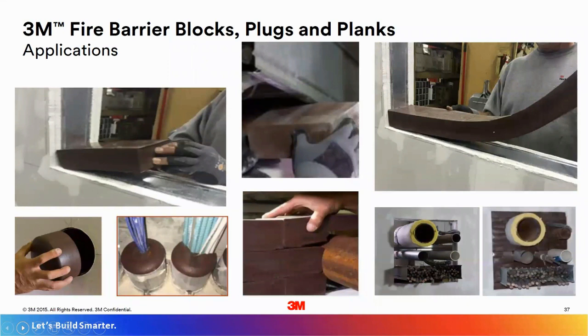And upon that urethane foam technology, we have a product called fire barrier blocks. These are available in blocks, plugs, and planks. Essentially, it's the FIP foam chemistry. These are cured material that's available in these various configurations. This is a great product to use for large openings, or if you have a situation like in the lower right-hand corner picture there, where you have a fire-rated wall assembly, for example, with multiple penetrating items. This is a great material, can quickly close down those large openings, and you would compress the material around any of the penetrating items. Any gaps, cracks, or small voids you had, you could fill with the FIP foam or one of our approved fire stop sealants.